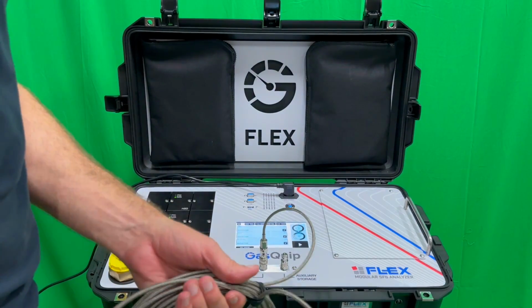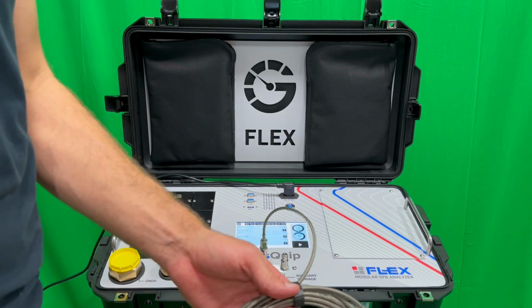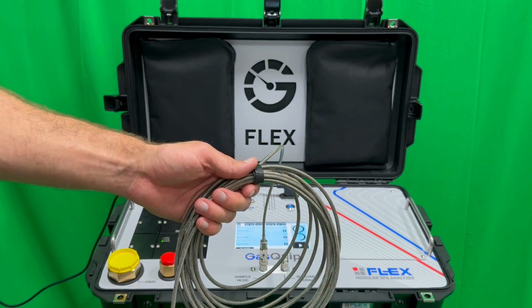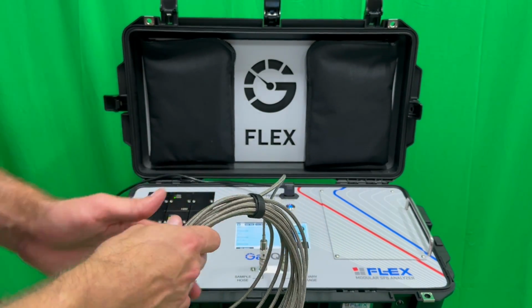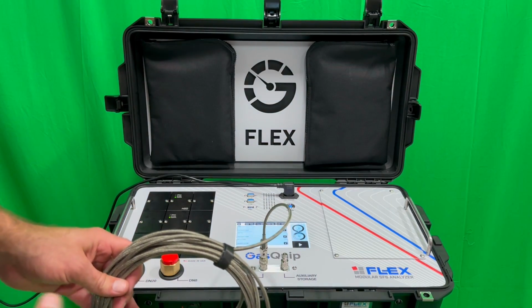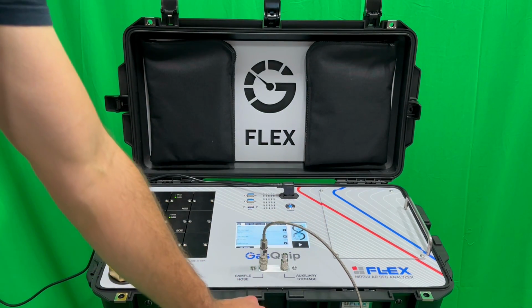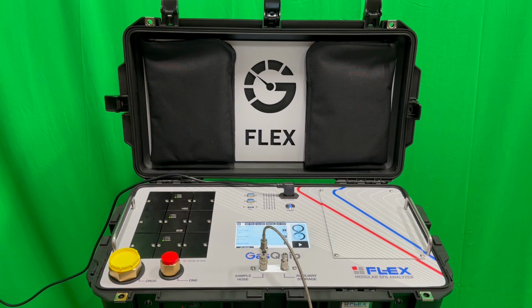Prior to doing any of that, we usually like to tell customers to pull a vacuum on their hose to remove any residual gases left over from prior tests. Maybe the device has been sitting on the shelf for a while, and you need to pull a vacuum on that hose and just get everything cleared out.